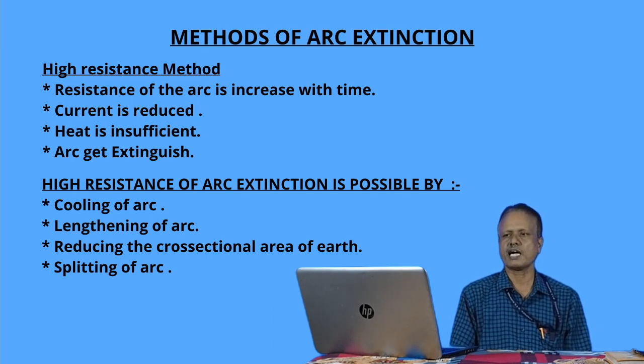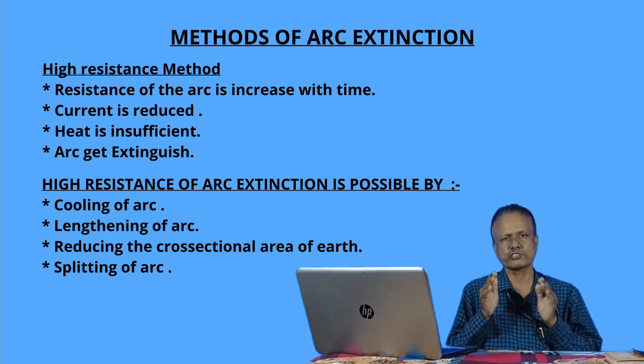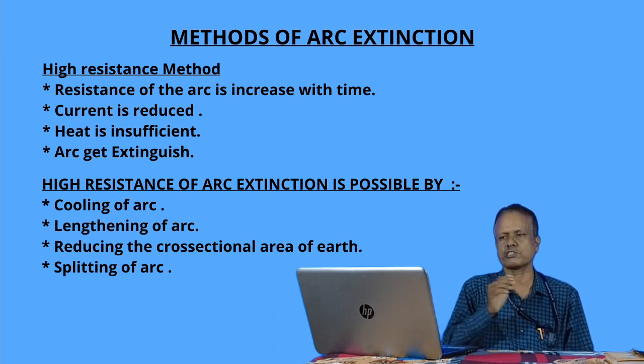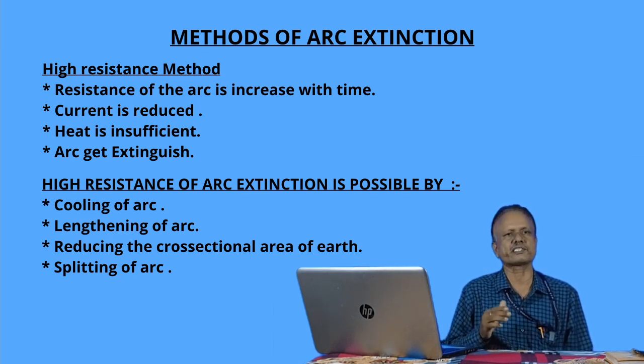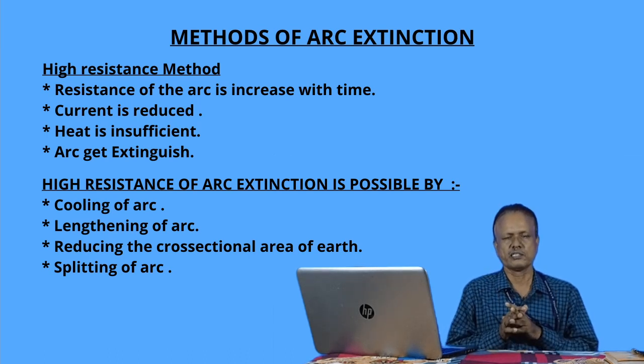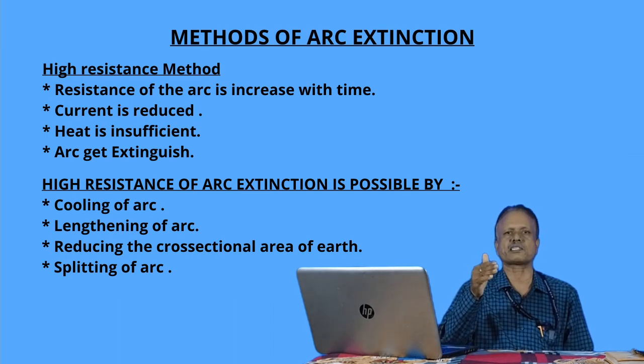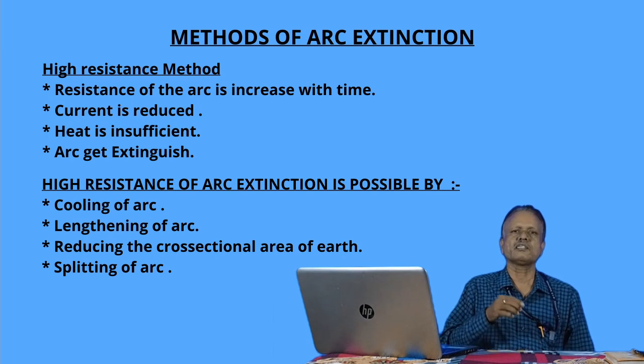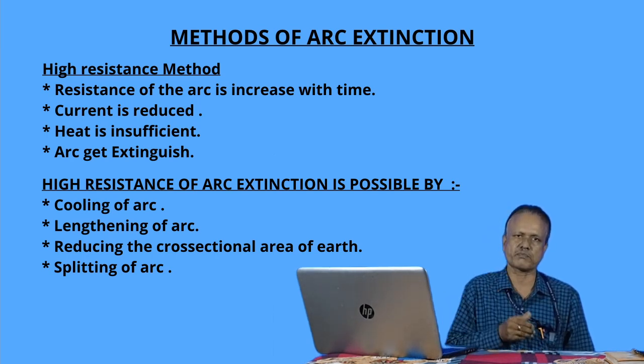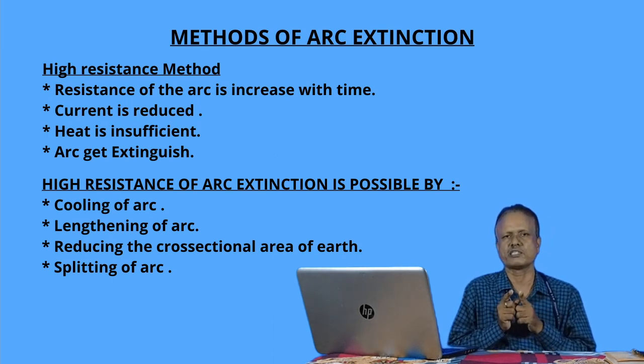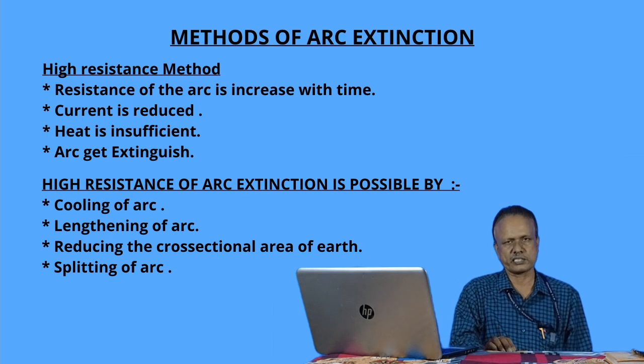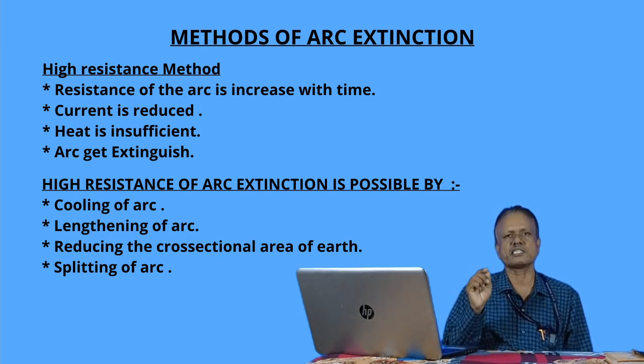So let us discuss the high resistance method. In this method the arc resistance is gradually increased so that the heat is not sufficient to maintain the arc and the current value is also reduced. That is why the arc is extinguished. This is the main thing done in the high resistance method of arc extinction. But the trouble here is that during this method, due to the resistive nature of the arc, a large amount of energy is generated inside the circuit breaker. So the circuit breaker should be designed in such a way as to withstand such mechanical shock. That is why this type of arc extinction method is applied in DC circuit breakers as well as air break type AC circuit breakers of low capacity.